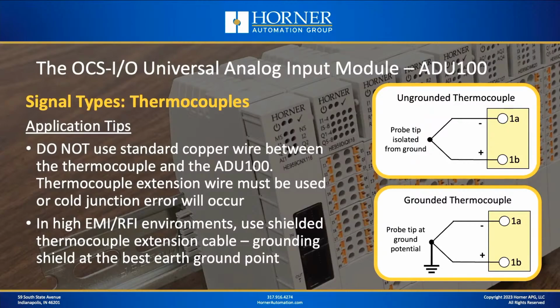Now let's talk about wiring and our application tips. On the right, you can see that thermocouples are wired to the ADU100 using the A and B terminals. There are two different types of thermocouple construction: ungrounded thermocouples and grounded thermocouples. With an ungrounded thermocouple, the tip of the probe, or the hot junction, is electrically isolated from ground. So if that tip physically comes into contact with the machine or the measuring point, and that machine is, say, a chunk of metal that is earth grounded, your probe is still isolated from ground. Whereas with a grounded thermocouple, there is no electrical isolation between the measuring tip and the probe itself, so if the probe touches earth ground, you're going to have ground potential at that point. That's the difference between ungrounded and grounded thermocouple sensors.